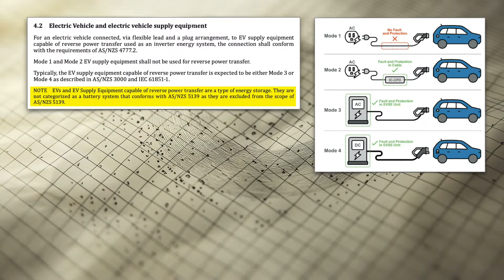So we're only allowing modes 3 and mode 4 for bidirectional, and that's because from a safety perspective, mode 2 is not appropriate - you could be unplugging that and have a live male pin on the end. Not a good thing. So only mode 3 and mode 4. And mode 3 is pretty unlikely to be used because that means the car has to have a 4777 Part 2 approved inverter built in. Whereas with mode 4, the car is just a battery effectively, and the mode 4 supply equipment is the device that converts and is compliant with the grid standard 4777 Part 2.